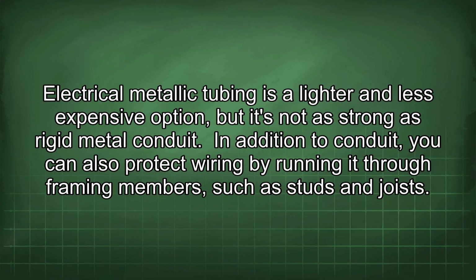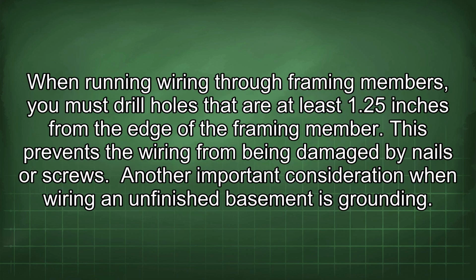Electrical metallic tubing is a lighter and less expensive option, but it's not as strong as rigid metal conduit. In addition to conduit, you can also protect wiring by running it through framing members, such as studs and joists. When running wiring through framing members, you must drill holes that are at least 1.25 inches from the edge of the framing member. This prevents the wiring from being damaged by nails or screws.